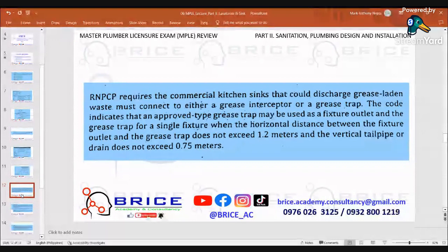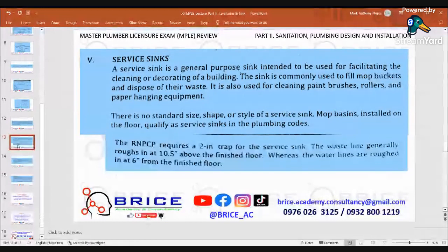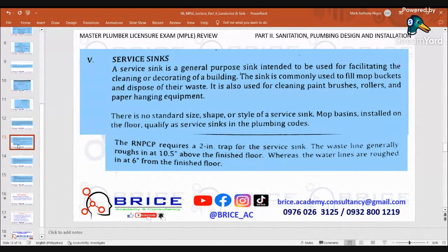Fifth: service sinks. A service sink is a general-purpose sink intended for facilitating cleaning or decorating of a building. It is commonly used to fill mop buckets and dispose of their waste, and for cleaning paint brushes, rollers, and paper-hanging equipment. There is no standard size, shape, or style. The RNPCP requires a 2-inch trap; the waste line is roughed in at 10.5 inches above the finished floor, while the water lines are roughed in 6 inches from the finished floor.